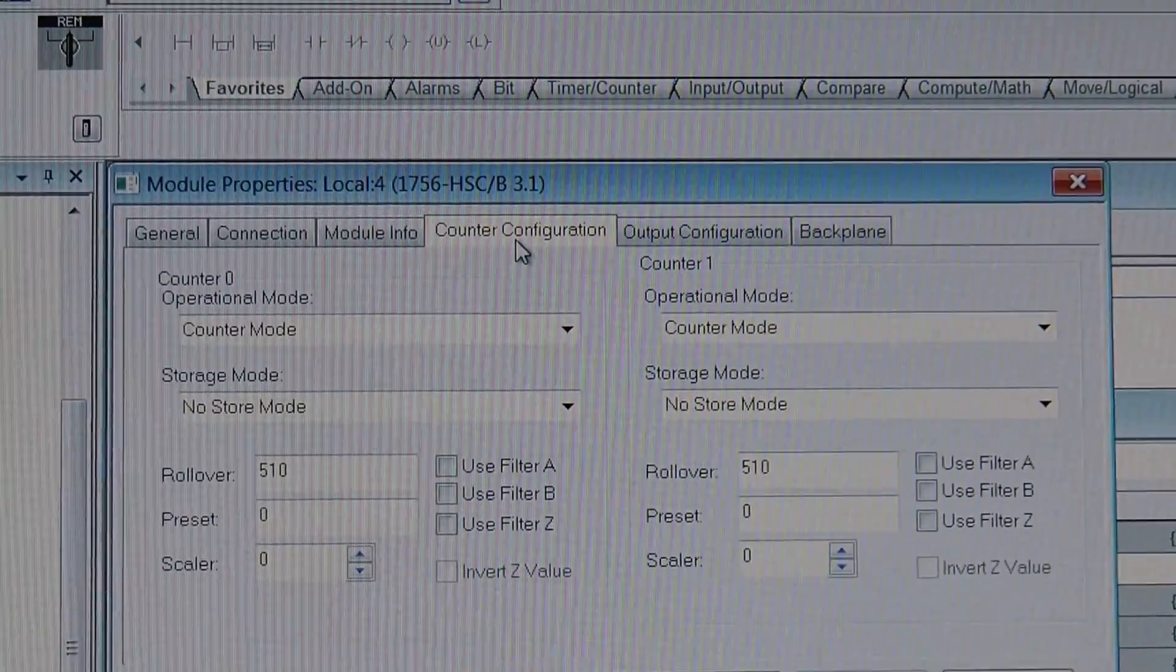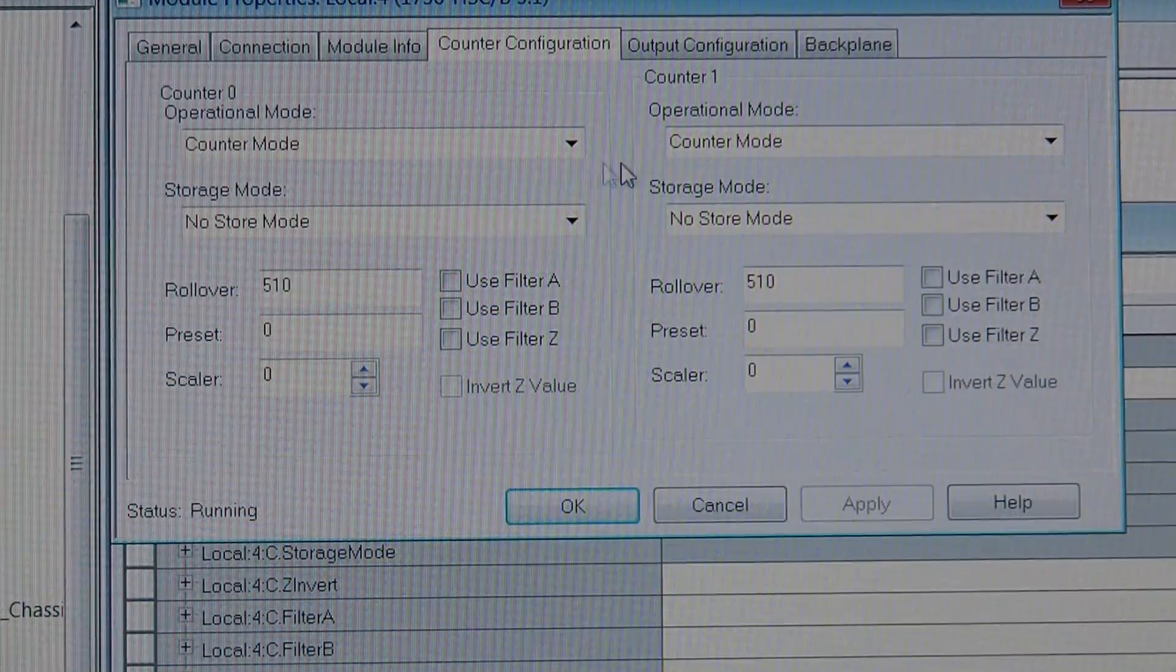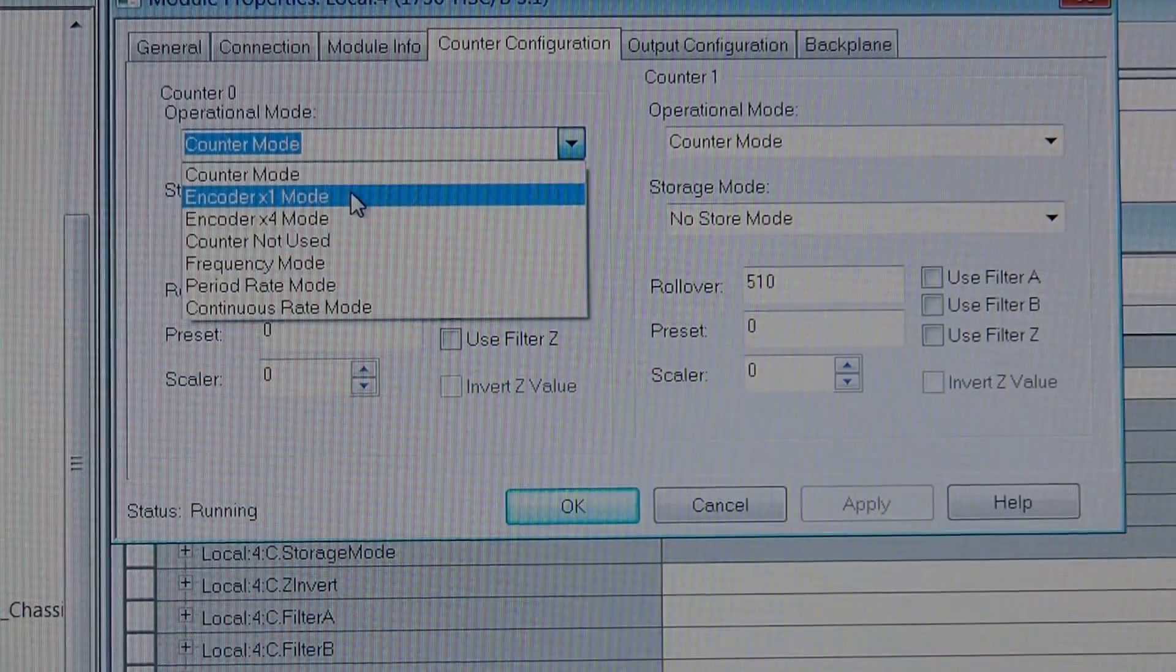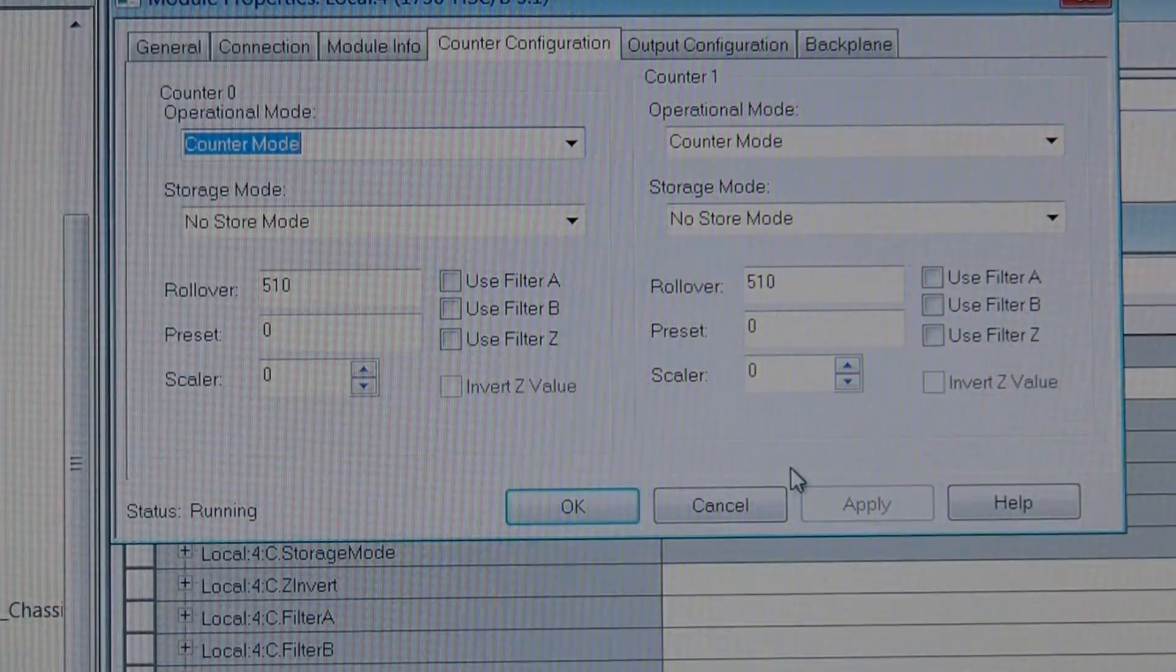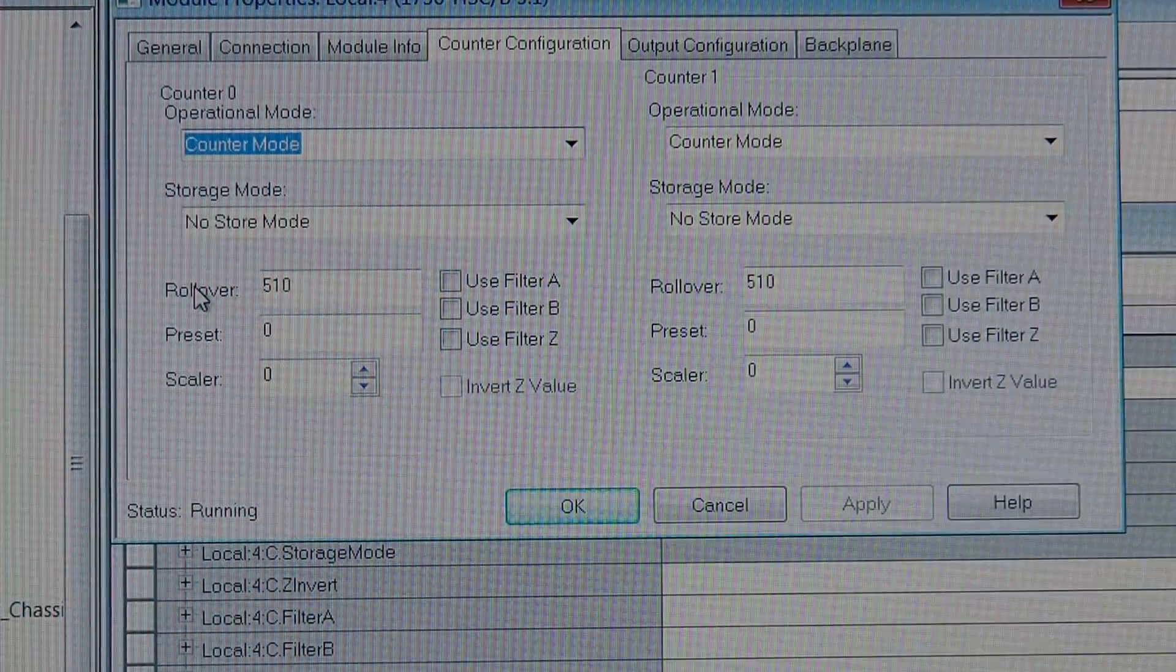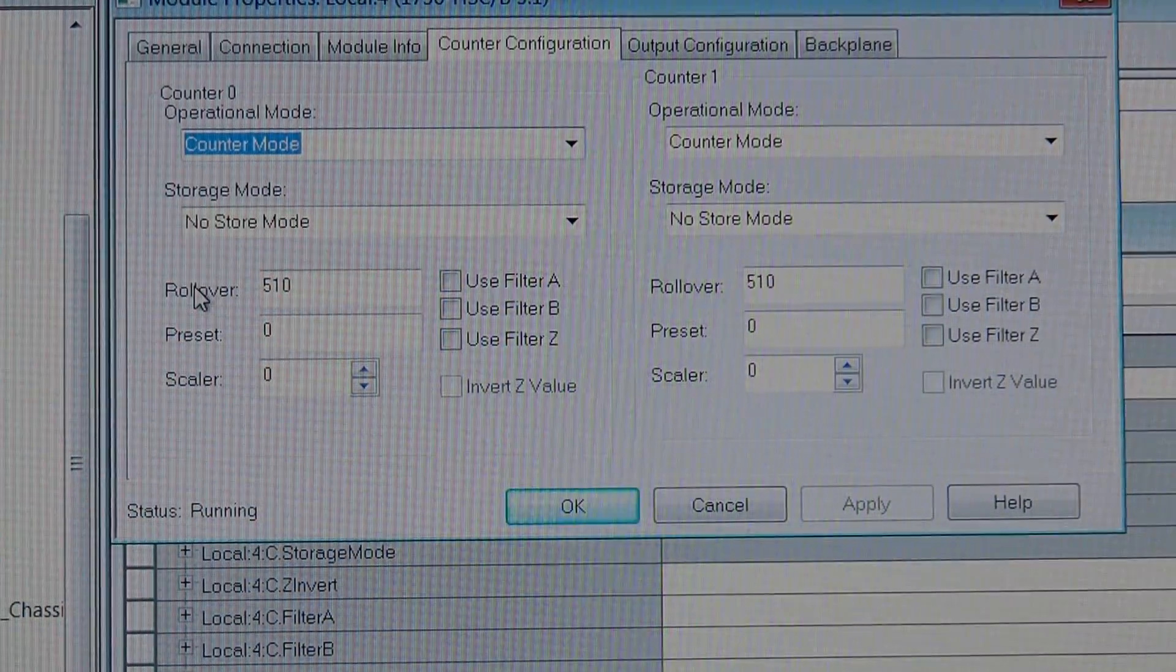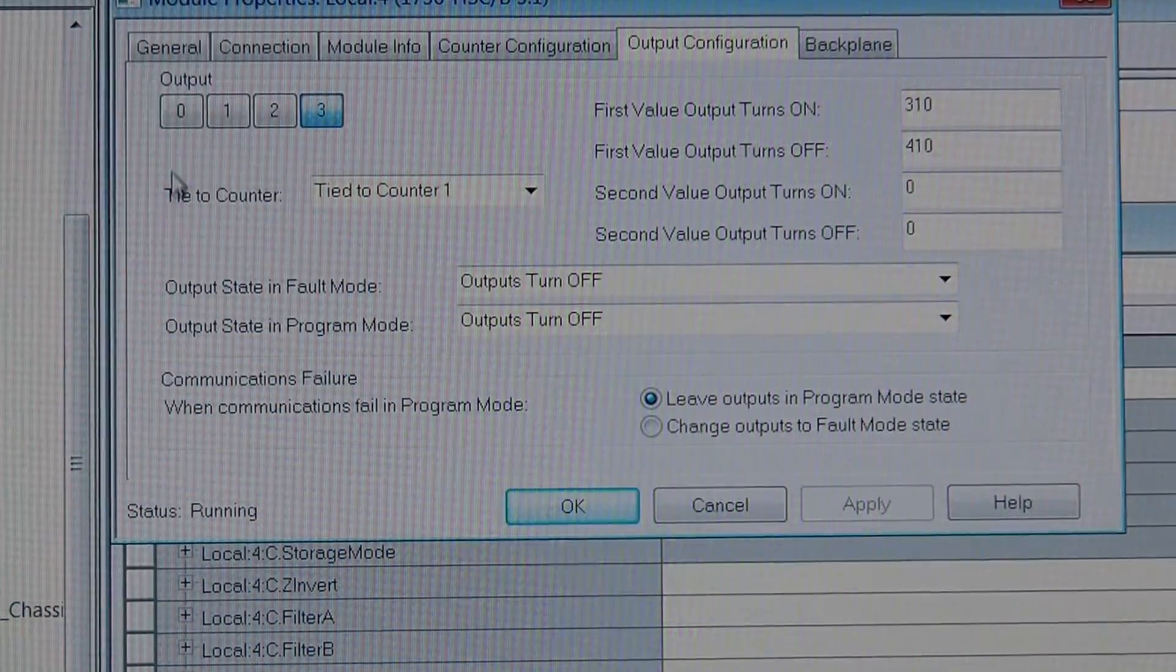So, the counter configuration is where you set up how your module, what is going to happen. So, in this case, we're in counter mode, but we could pick encoder mode. We could pick any of those there, and both channels, and our rotation is set up at 510, which is where we roll over, and back to zero. So, now we go to the output configuration.